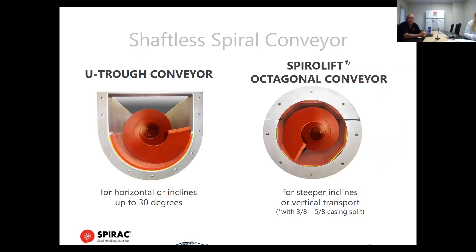Here are a couple different trough configurations. The one on the left is a U-trough conveyor — typical. We use that for up to 30 degrees, sometimes 35 degrees. When we go from 30 or 35 degrees to 45 degrees, we use the octagonal trough configuration, as well as in vertical applications. Both units are pretty robust and fully sealed.